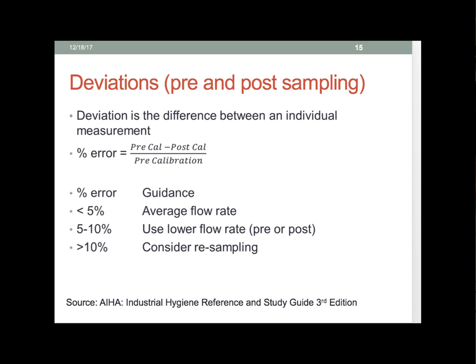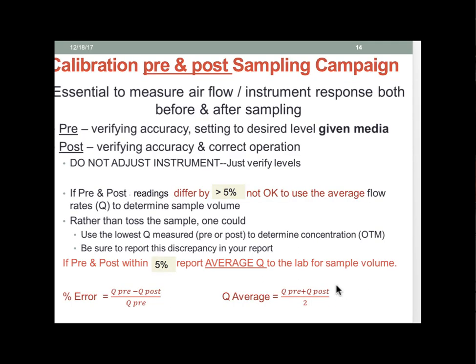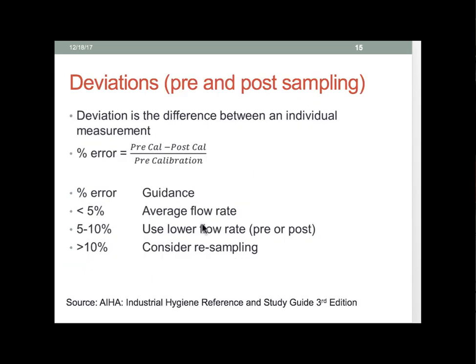To state that again: we calibrate before we sample, then we sample, then we calibrate after we sample, and we have these two flow rates. If they differ by less than 5%, we take the average — flow rate before plus flow rate after divided by 2 — and use this to calculate our sample volume. If they differ by between 5% and 10%, then we use the lower of the two flow rates. If they differ by greater than 10%, we should consider resampling.